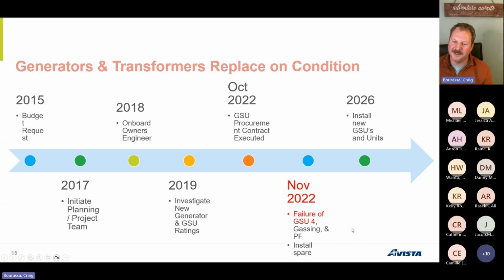It was gassing, power factor showed it was failing, so we installed the spare. These things won't actually get replaced until 2026—it takes 10 years to replace it. So for a run-to-failure asset, you've got to try to identify failure 10 years in advance.